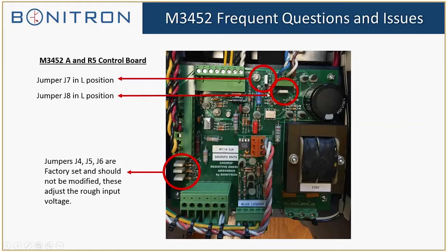Oftentimes when I tell customers to do this, they will ask me right away what these three jumpers down here are, J4, J5, and J6. These are factory set. Basically, these control the input voltage for the board, and these should not be messed around with willy-nilly. The reason for that is while you could change this and the board could think it should be getting 240 instead of 115, the control transformer is actually what controls it. This just controls the logic. So customers should not mess with these jumpers, but only change these jumpers as required for master and slave operations for the A and R5 control boards.